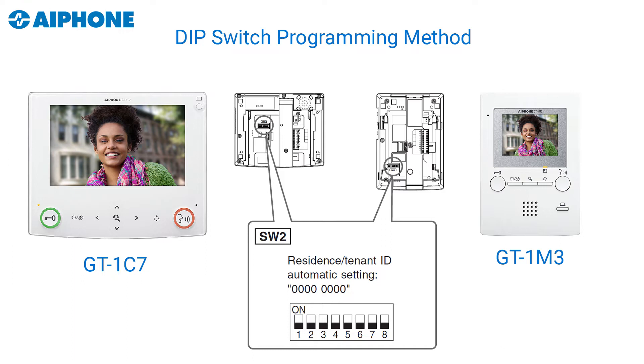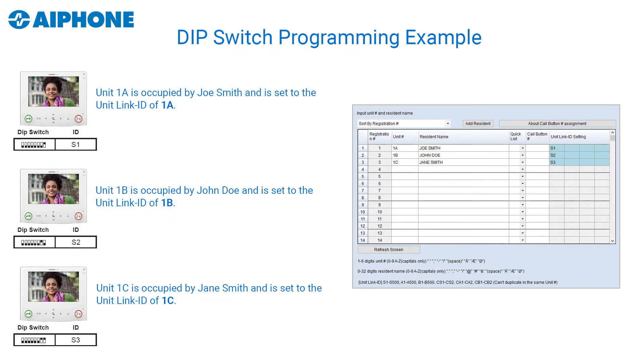With the dip switch method, each individual apartment gets its own unique ID set by switching the dip switches on the back of the units. Each dip switch setting has an associated software ID which must be added with our software tool to the system. These software IDs get placed in the unit link ID settings in the software tool. Please take a moment to read the examples provided to get a better grasp of the concept.